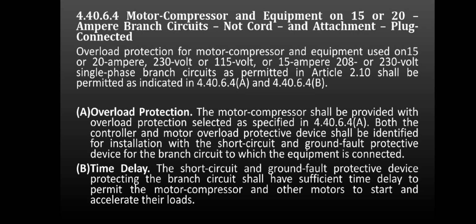This slide explains the rules of protecting motor compressors, such as those found in refrigerators or AC units that run on a small circuit, like a 15 to 20 amp branch circuit. These machines need overload protection to avoid overheating or burning. The short circuit device must allow enough time for the motor to start because motors use more power during startup. Both controller and overload device should match the protection system used in the circuit. In simple terms, this slide shows how motors must be safety protected on small circuits.